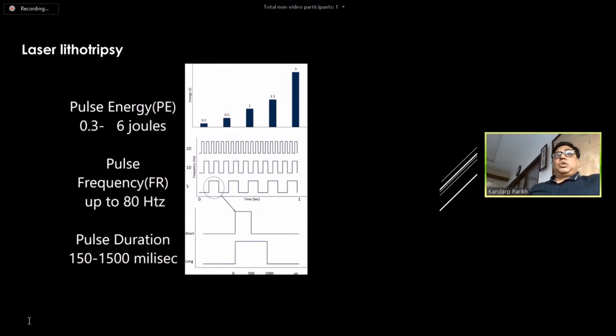And so with a high power laser, you can exceed your energy delivery to 6 joules. Energy will do three important things. One is the fragmentation. Fragmentation is much better if you increase the energy. That is one. But another disadvantage of it is that it produces retropulsion of the stone. And when there is retropulsion, the stone will move away from the laser fiber. So you have to readjust the laser fiber, and that is time consuming. And third important thing is the backburn effect on the laser fiber. So the laser fiber is eaten up quite quickly if you keep on increasing the energy.